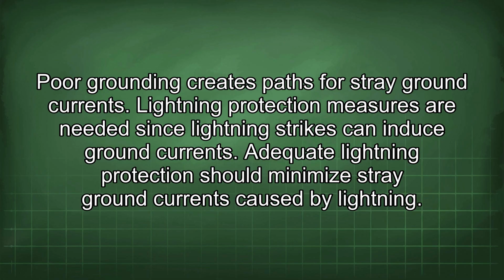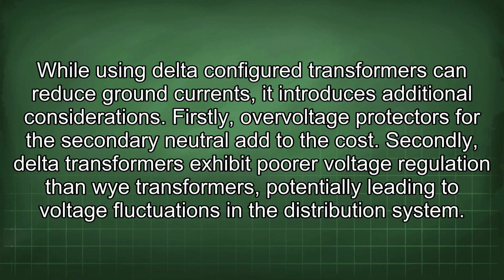Lightning protection measures are needed since lightning strikes can induce ground currents. Adequate lightning protection should minimize stray ground currents caused by lightning. While using delta-configured transformers can reduce ground currents, it introduces additional considerations.